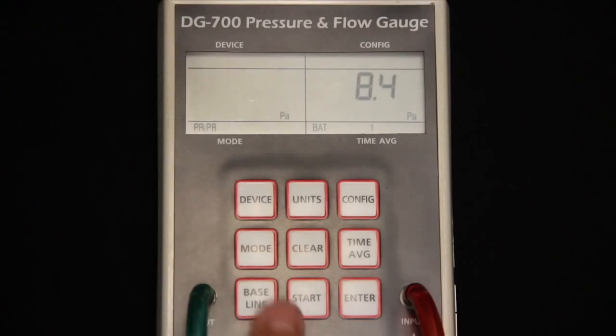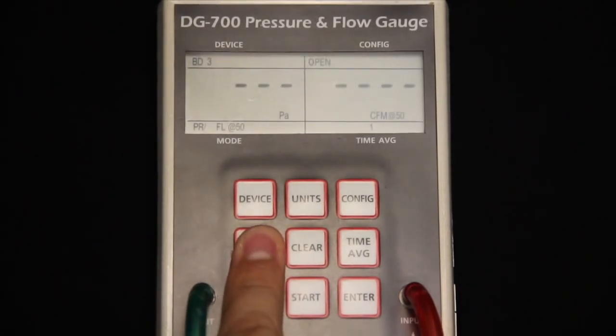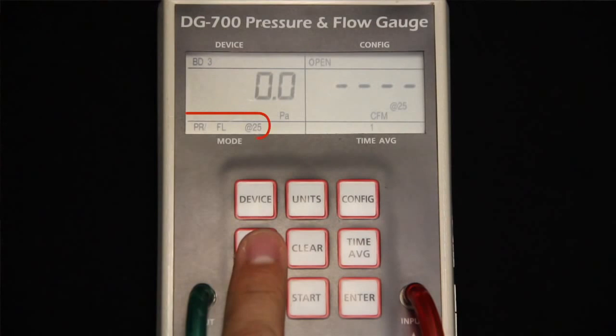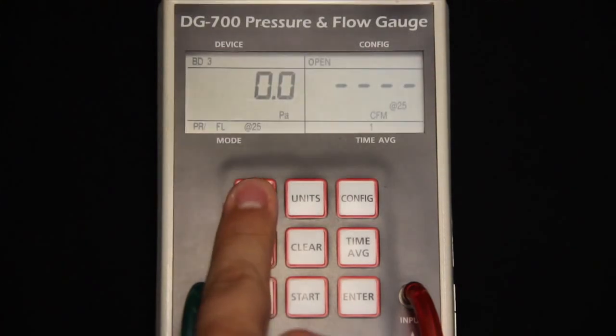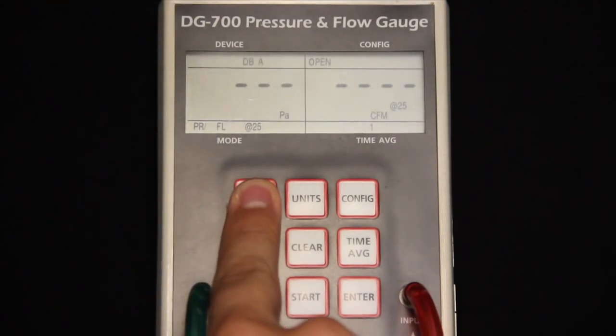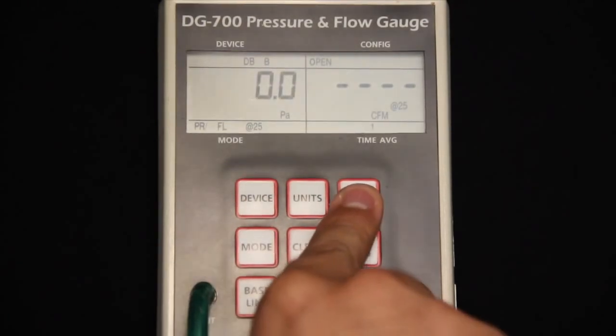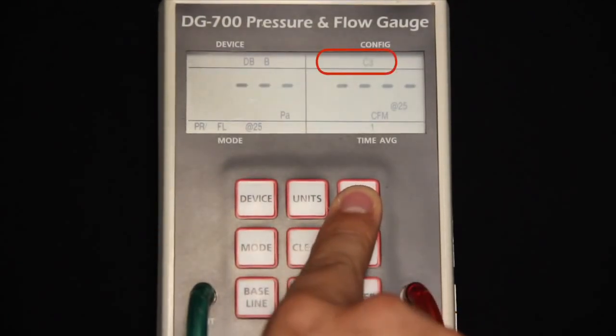Since side B of the digital gauge measures fan pressure, it can be programmed to calculate the CFM passing through the fan. To program the gauge for the total leakage test, press the Mode button 3 times so that it displays pressure and flow at 25, PR/FL at 25. Press the Device button 4 times to select DBB, or Duct Blower Series B. Press the Config button to select the appropriate ring on the gauge, such as A1, B2, or C3. Now you are ready to test your duct system.